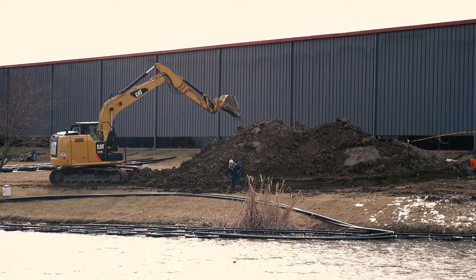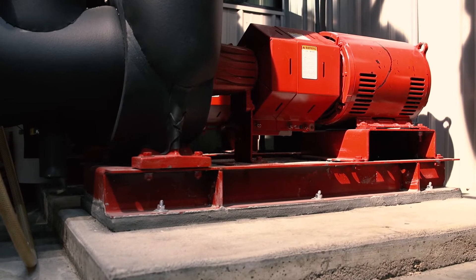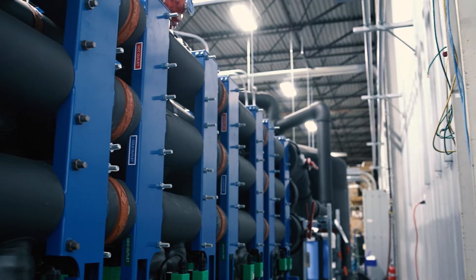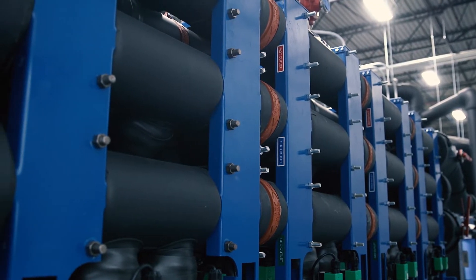Twelve circuits of new pond loop were interlaced with the older 240-ton system in our 3-acre pond. All pond loop flow is managed by the 30-horsepower variable speed base-mounted pumps in the loop mechanical room. The 200-ton chiller bank includes 100 tons of variable speed and 100 tons of dual-stage modular chillers using an integrated six-pipe rack.